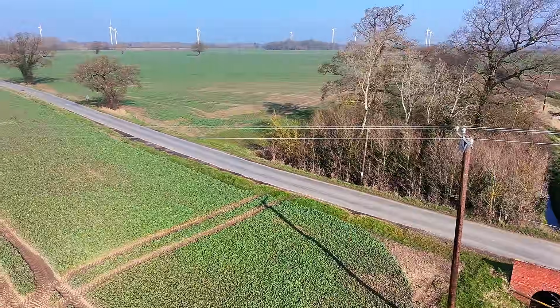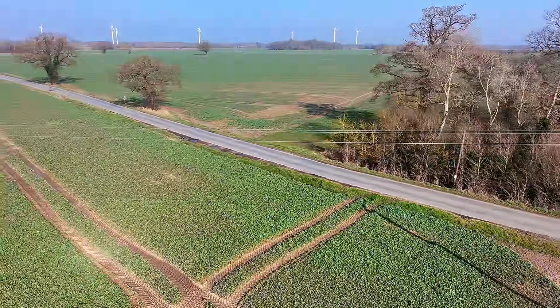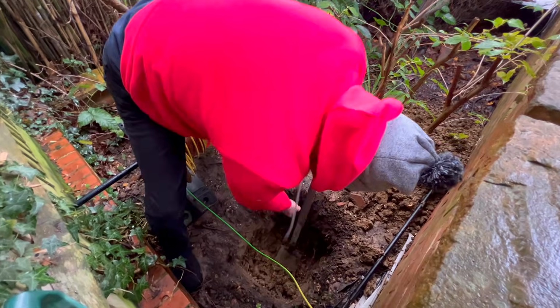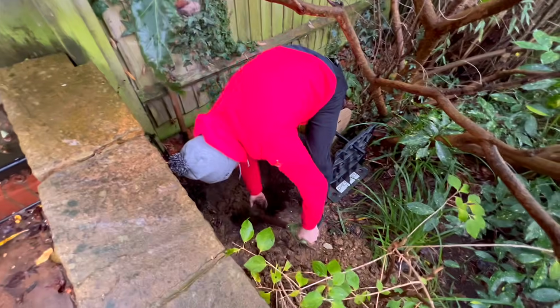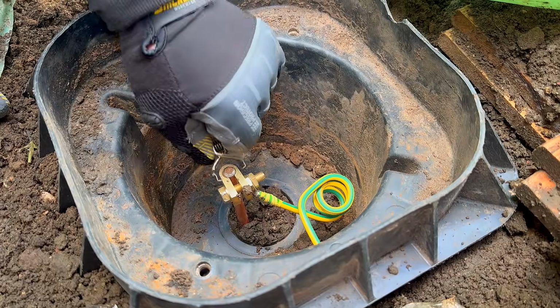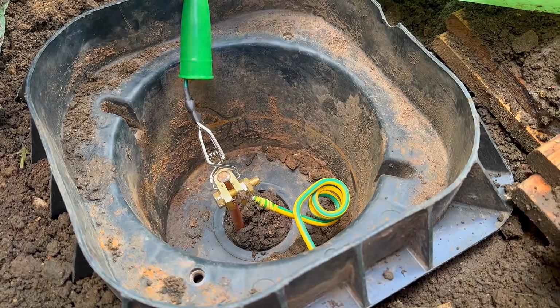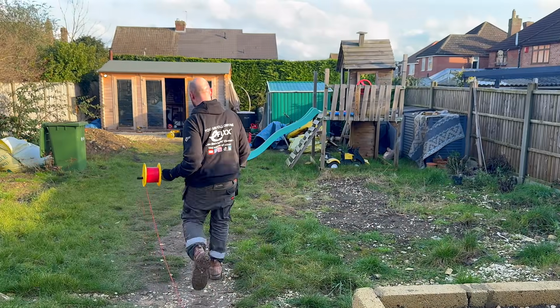Different ground conditions allow that current to spread more easily than others. But I'm going to be diving into that in a later video on soil resistivity and site surveys. For now, all you need to take away is this: if the soil affects how current spreads, then it affects how well the earthing system works. But if we're just testing the earth fault loop path, can't we just do an earth fault loop impedance test? It's a fair question. The earth fault loop impedance test measures the earth fault loop path. But an earth electrode resistance test focuses on the performance of the earth electrode itself and how it interacts with the ground around it.